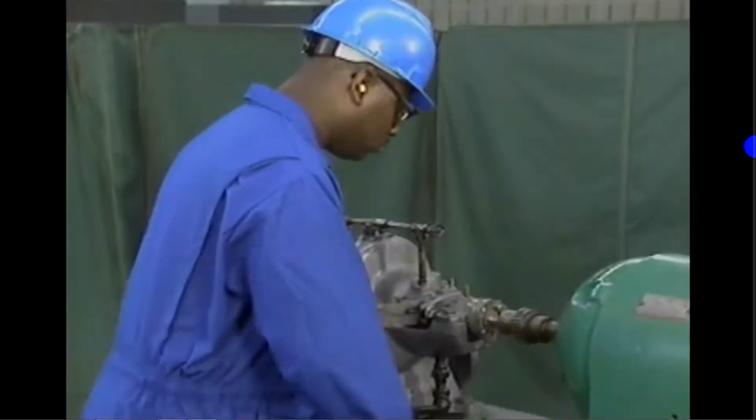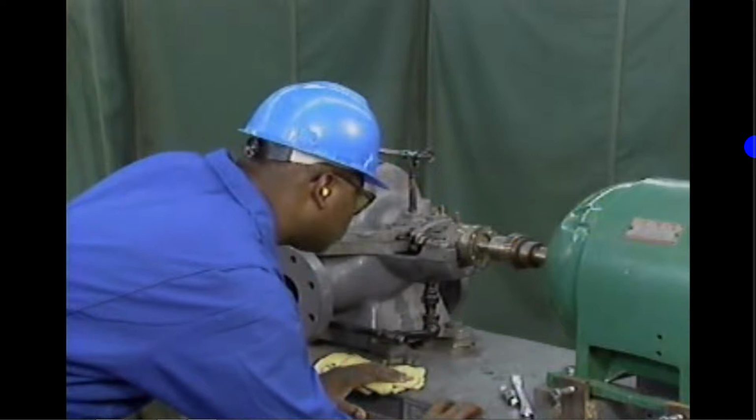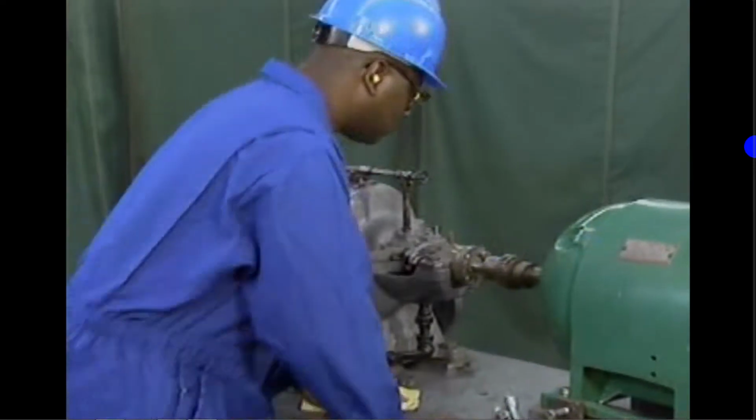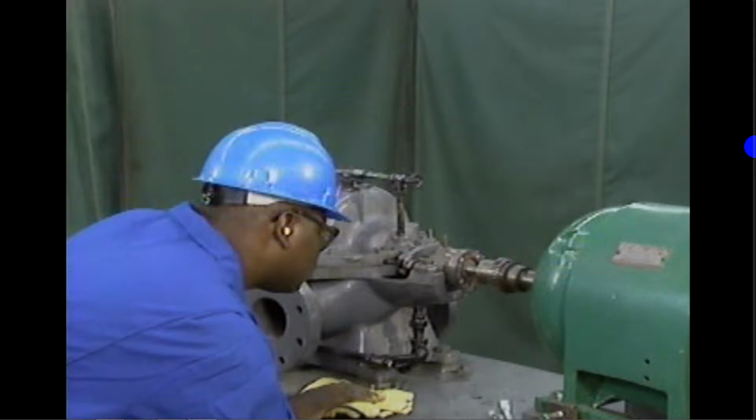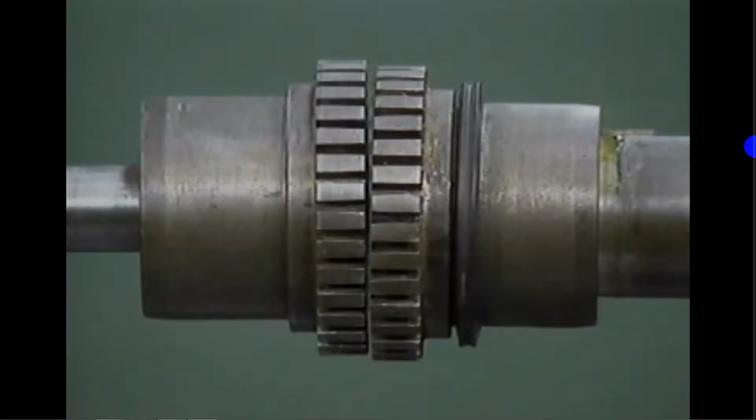The mechanic begins the procedure by visually inspecting the coupling hubs to determine, as best as possible, what needs to be done to align the two shafts. From the side view, it looks like the hub of the motor is slightly lower than the hub of the pump, and that the motor is angled downward. In other words, it looks like there's parallel and angular misalignment in the vertical plane.